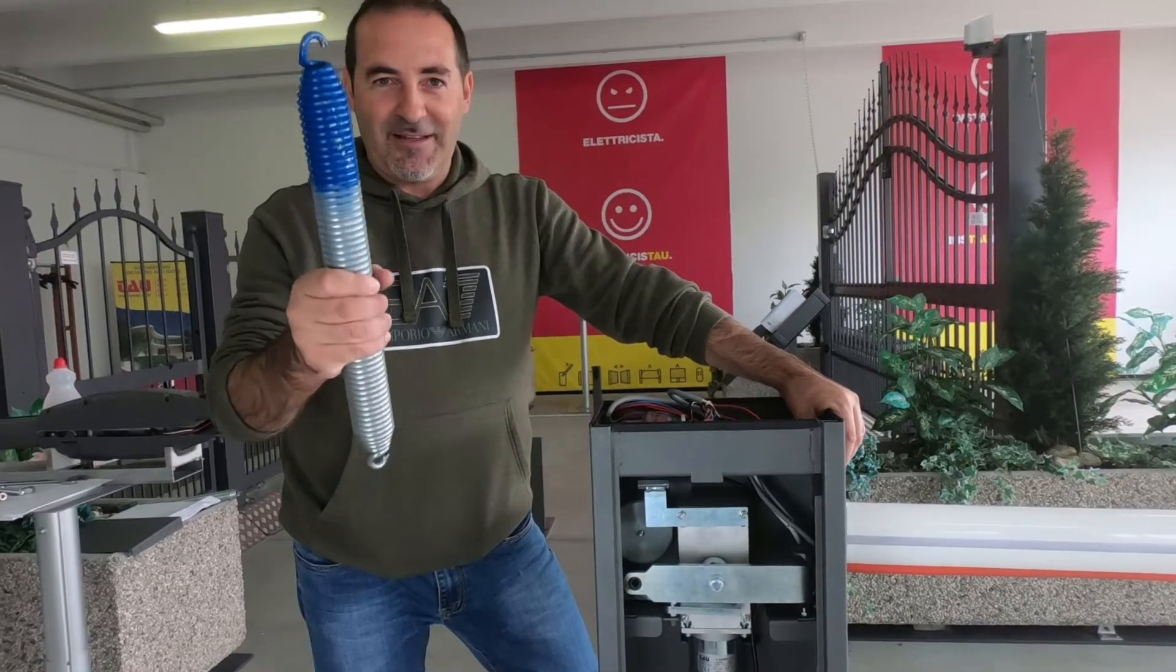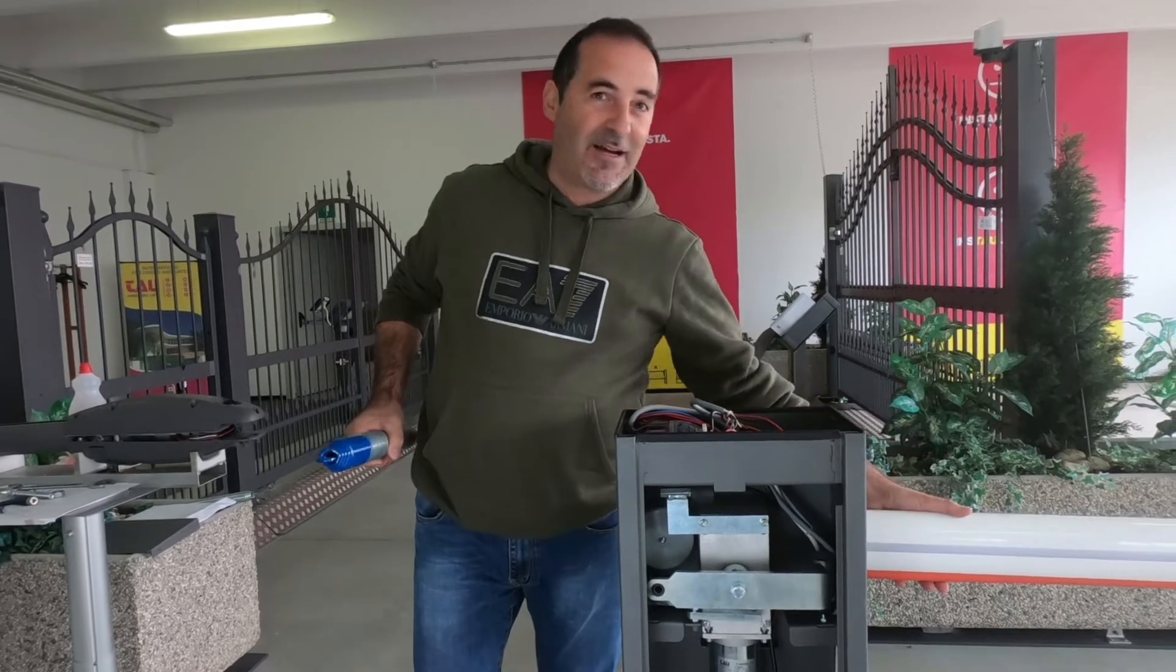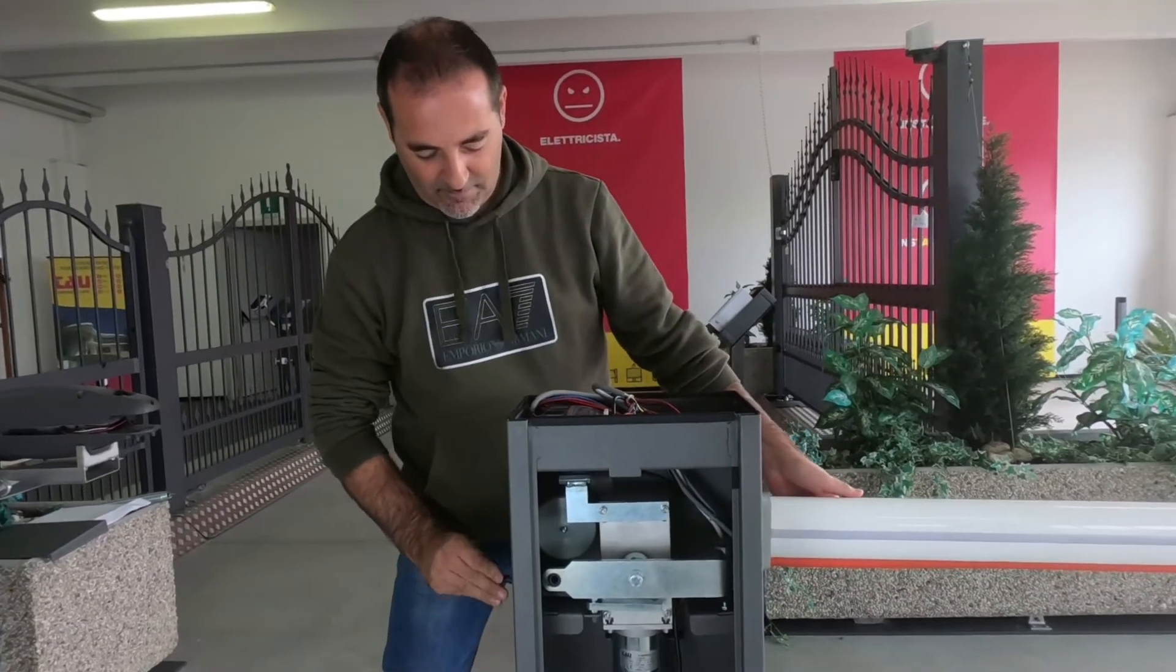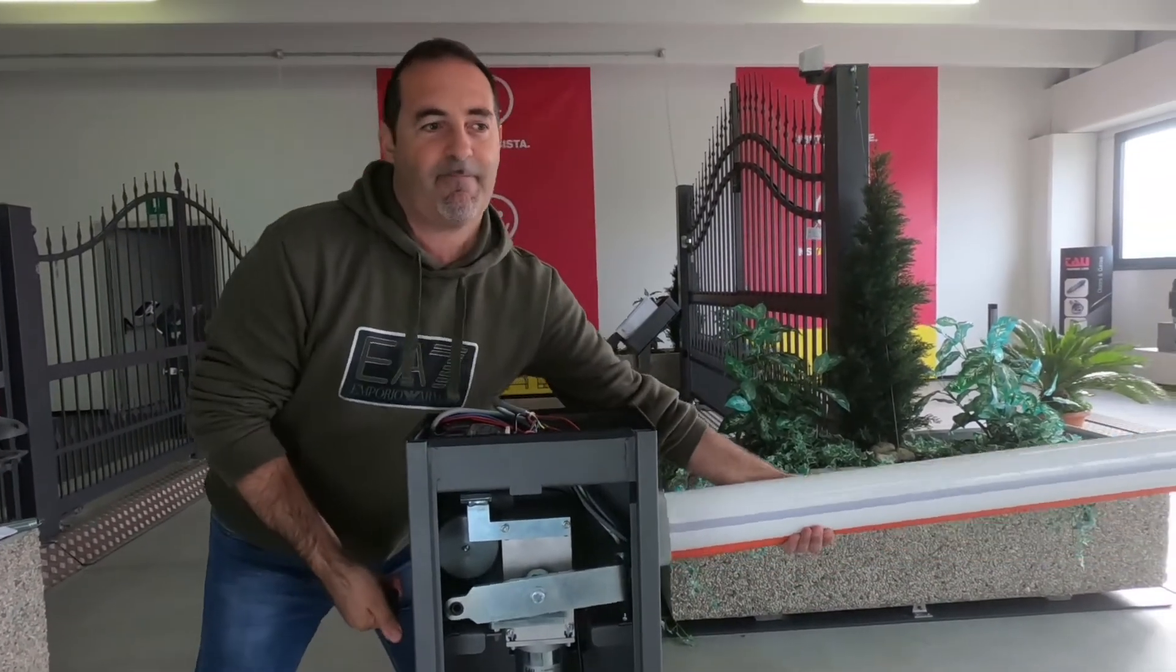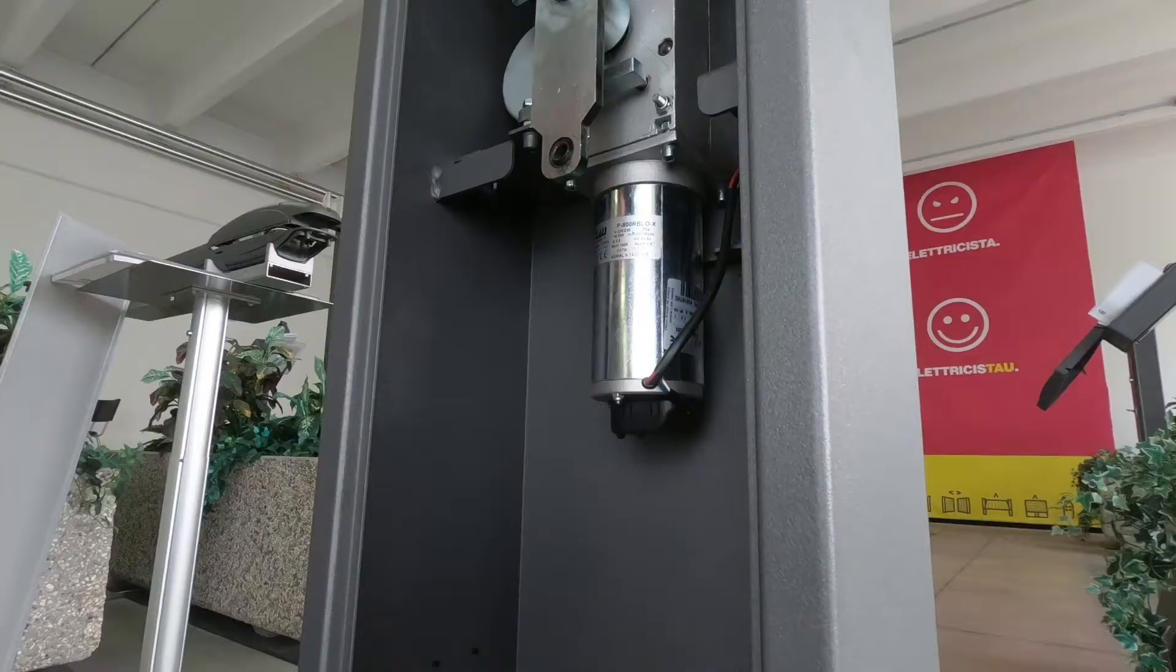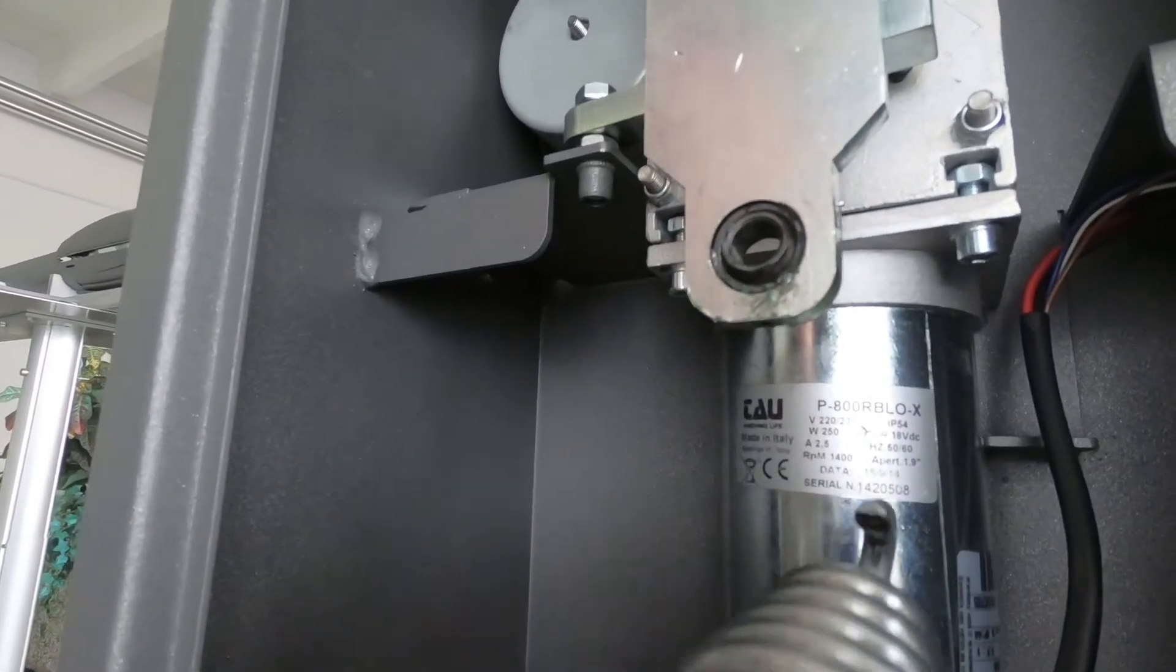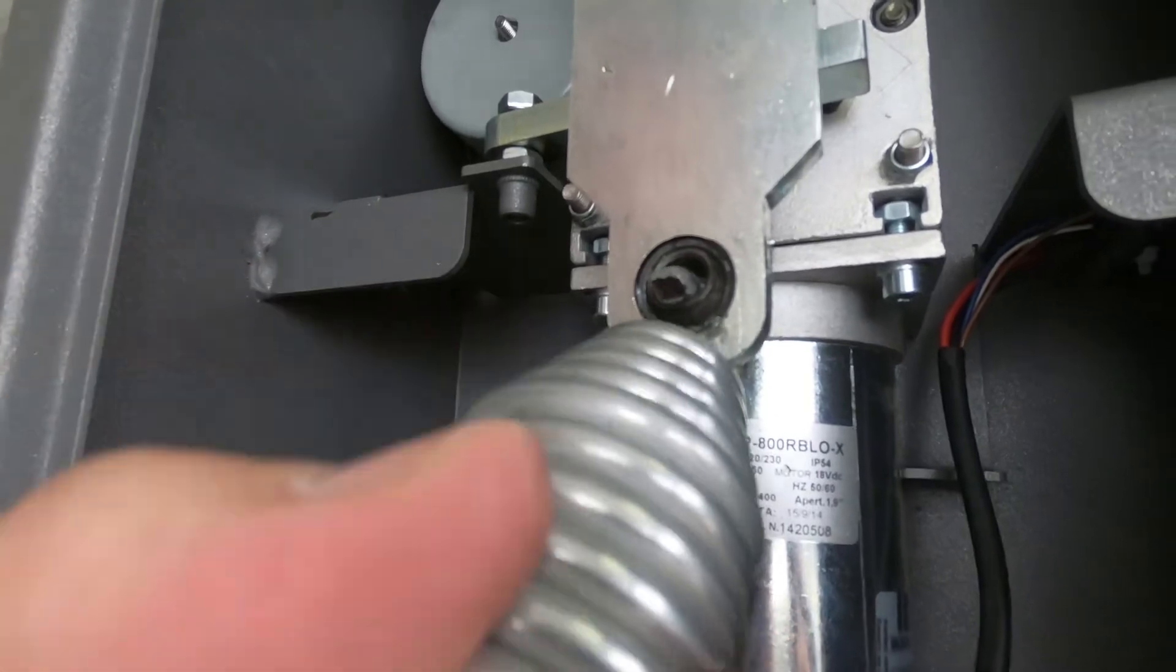We start by placing the boom in a vertical position and locking it with the key release mechanism. In this way we will ensure that the boom does not fall out while we perform the operations. The spring must be positioned inside the cabinet by hooking it on the top of the gear motor.